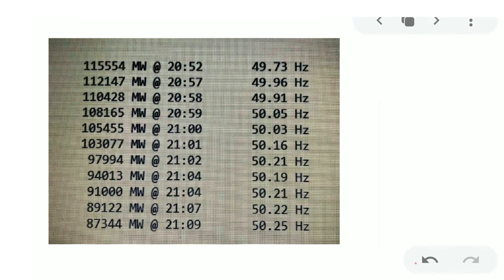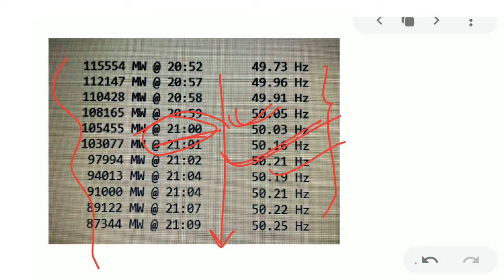Here you can see data of frequency and the demand. As you can see, from 2052 to 2109, there was a decline in the megawatt generation from the generator. But as you can see, the frequency has been well maintained from 49.73 hertz. That was at 2052, and this was the time when everyone turned off their lights at 9 p.m. So here you can see there was sudden increase in frequency, 50.05, then 50.03, then suddenly it went to 50.16, 50.21, but it was more or less near this 50 hertz.